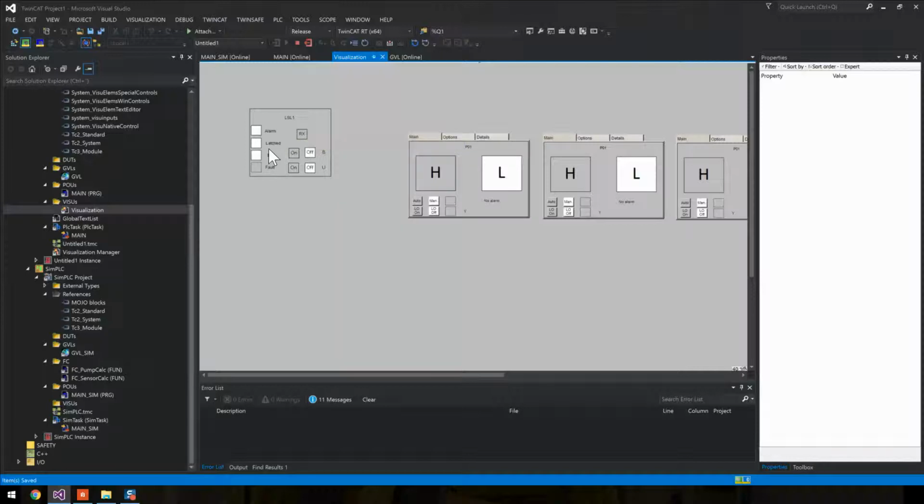Yeah, so here's an alarm. We can try and reset it. That's not working. We can block it. It's still latched, so it's not off. It's still there. So you can see. Oh, sorry. If we remove the blocking, the latch value will go through. So we blocked the alarm. There's no alarm, but the cause of the alarm is still there.